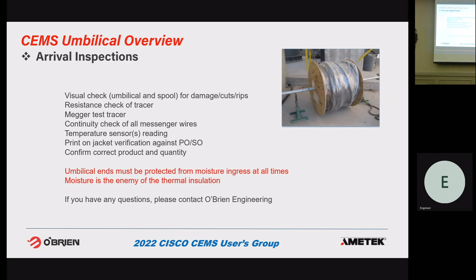Slide. It's also good to do a tracer check. So get to the ends of the bundle. If the ends are flush cut, we'll put shipping caps, there's vinyl caps over the ends. Pull those off. Do a quick check of the tracer. Just do a resistance check and a Megger test. Record those values. Put the shipping caps back on.